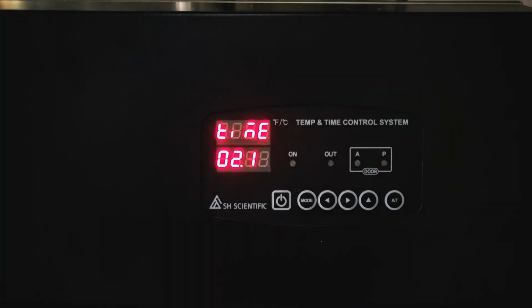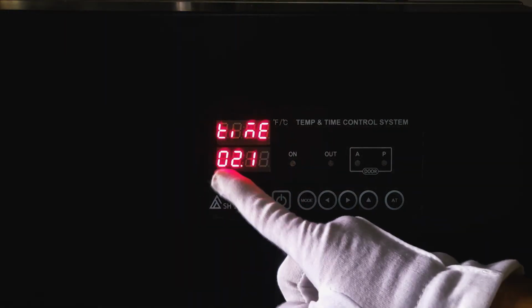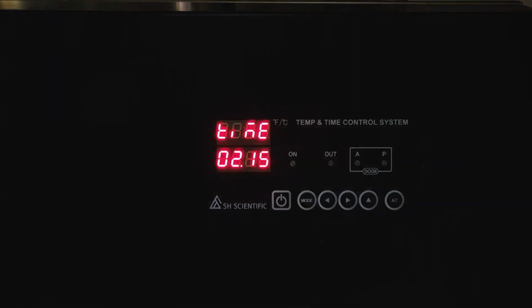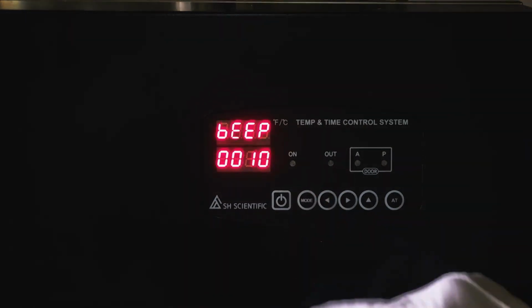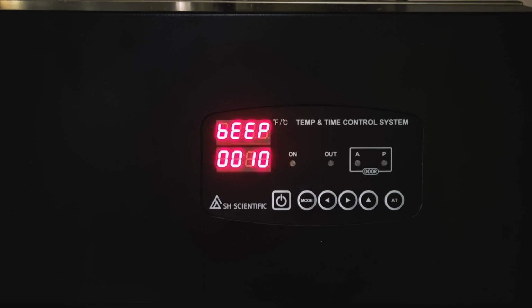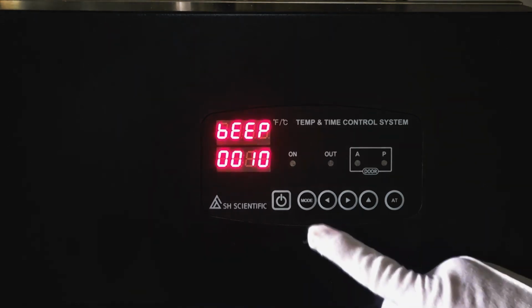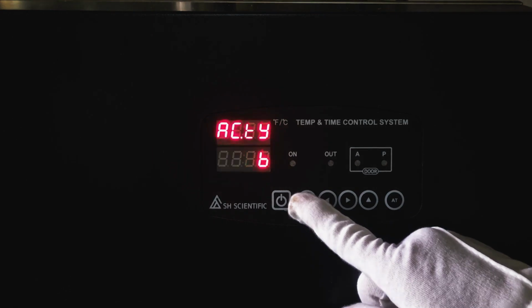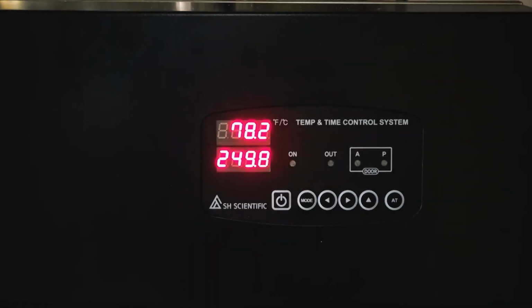The unit here is hours and minutes, with a max of 99 hours and 59 minutes, but I've selected 2 hours and 15 minutes. Just like before, press the mode button once to enter the selection and go into beep settings, which will tell the autoclave whether to alert you at the end of the sterilization cycle. The unit here is seconds, and I've selected 10 seconds for now. Then, you can choose an ending mode of A, B, or C. I'll explain what these mean a little bit later. For now, press mode to go into standby, then press the power button to start the autoclave.